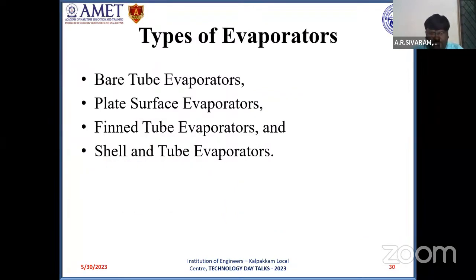And coming to the types of evaporator, there are bare tube evaporators, which are used in freezers, and plate type evaporators, where normally the tubes are embedded in a plate, and this is used for most applications. Then there are finned tube evaporators and shell and tube evaporators, which are used for very high capacity refrigeration systems.